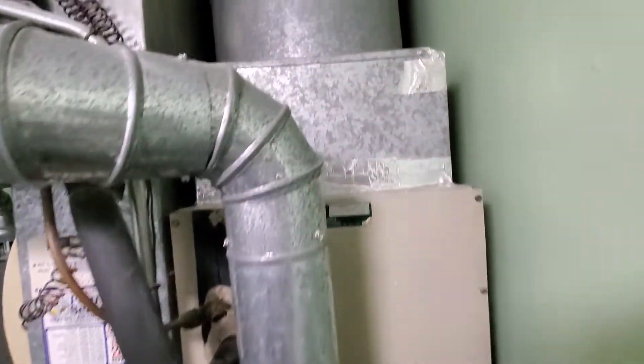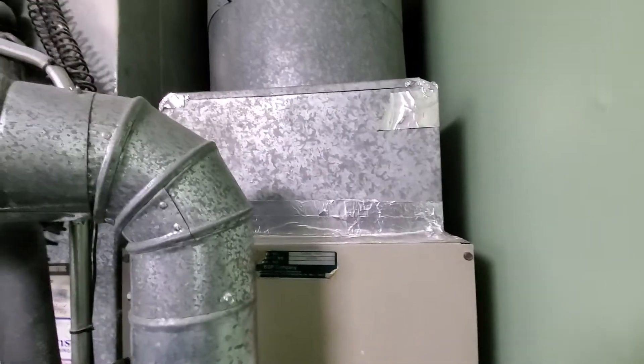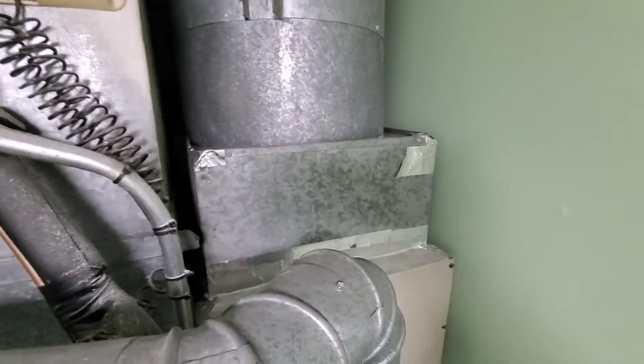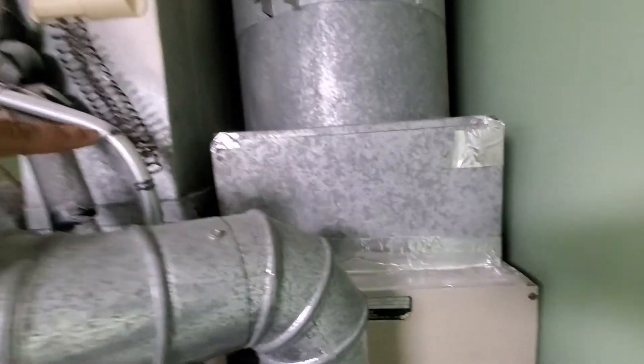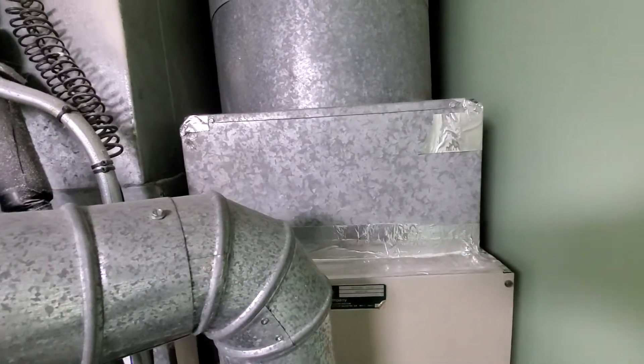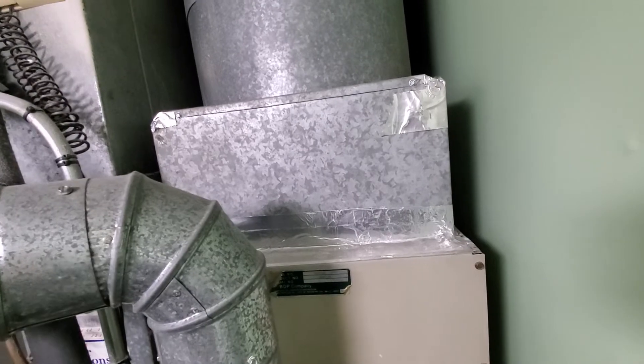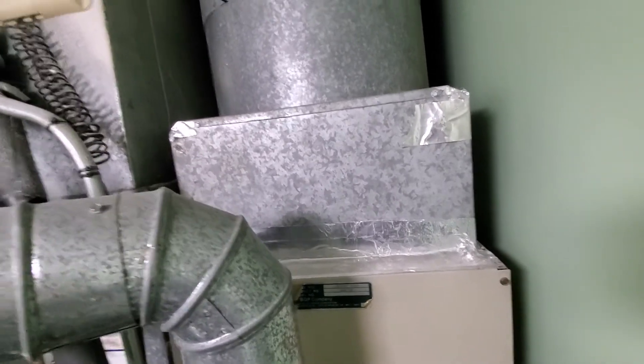So not sure how you guys want to do it, but I'm just addressing it to the installation team whether a plenum would work there. You can remove that and do a plenum, or if it needs to be actual duct with galvanized steel.